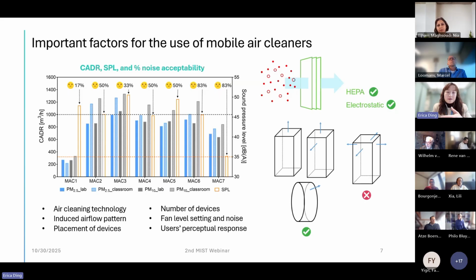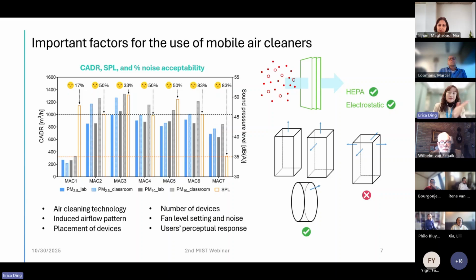Then the induced airflow patterns, which made a big difference. We found that mobile air cleaners with an upward air supply, either vertically up or angled, can better distribute clean air in the room than those with a horizontal air supply. This explains why MAC1 had a much lower CADR than the other MACs, because it's the only one with a horizontal air supply.